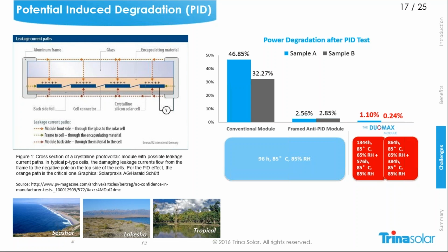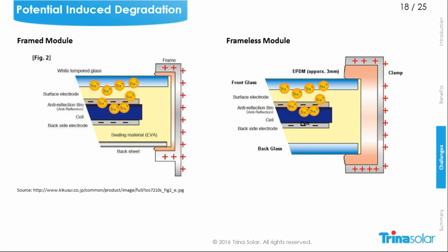That also the impact, the degradation effect, can be higher on the modules, which means a glass module has its advantages. On the next slide, I want to show the differences and the advantage of having a glass module for higher voltages. As already explained, it's a potential difference, so there will be a diffusion process in the module which leads to degradation of the cell. And here we have a potential difference between the cell and the frame.